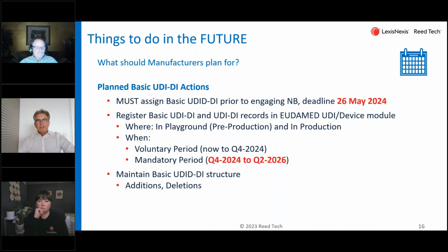And of course, you need to keep maintaining your basic UDI and UDI structure. So keep going back to that. Is it still valid? Is it still correct? Or do I need to split up things, or can I delete items? Those things, so you need to look into that. It will require a lot of work. But if you do your UDI well, it will help a lot in making notified bodies navigate through your documentation. It will make life easier if you do it well. That's all. Thank you. Very good.